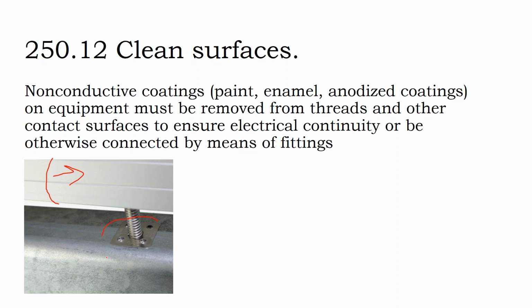And so when we're installing our grounding washers between our metal module frames and our metal racking, there's a few things you want to make sure to do, and one is to make sure that these surfaces are clean, and that clean is to make sure that these grounding washers are flush. These grounding washers also have little spikes that go into the metal to ground, and you need to make sure that they actually get in there. If you're installing a module using a grounding washer, and later you take the module off and you don't see any indentations into the metal module frame, then you probably don't have that metal module frame being grounded. So you can do continuity tests on site to make sure your system is properly grounded.